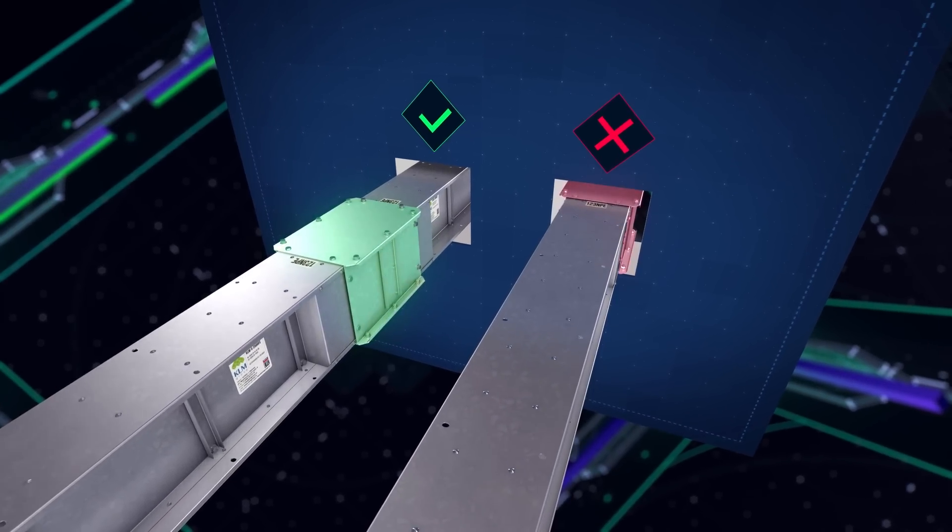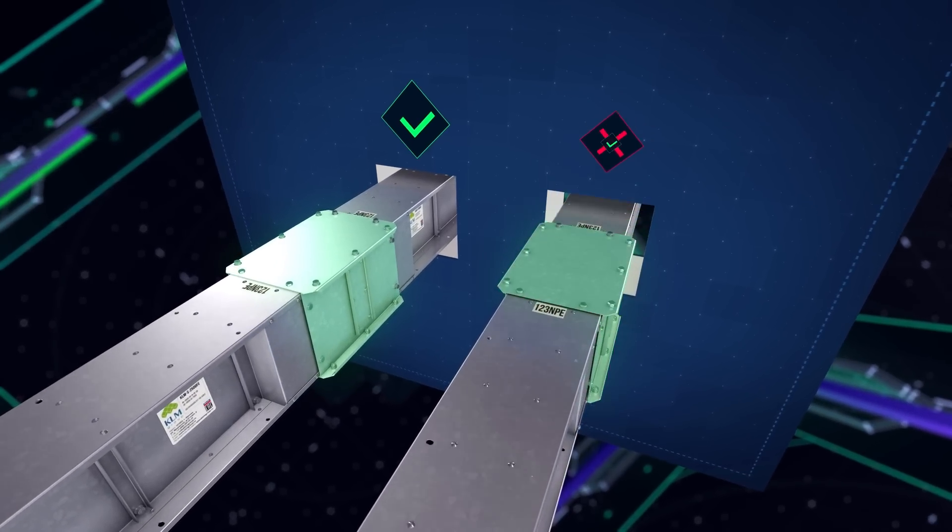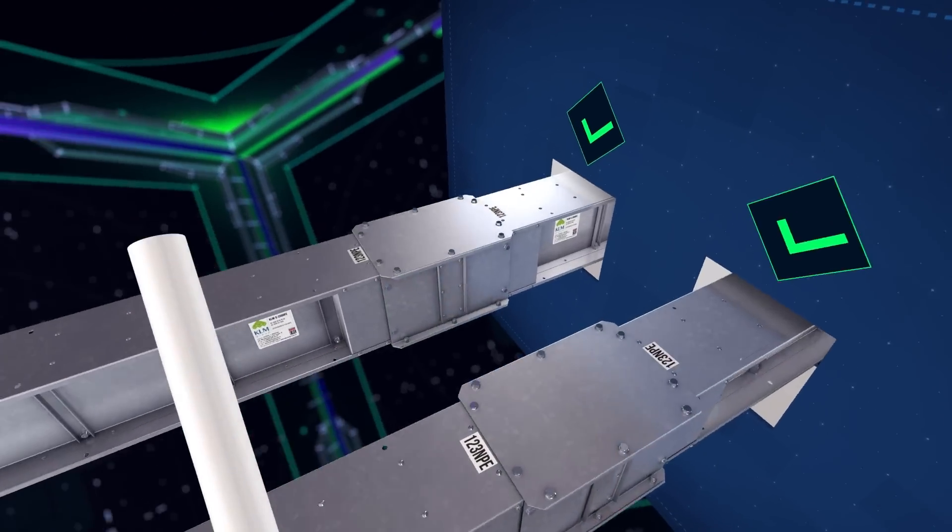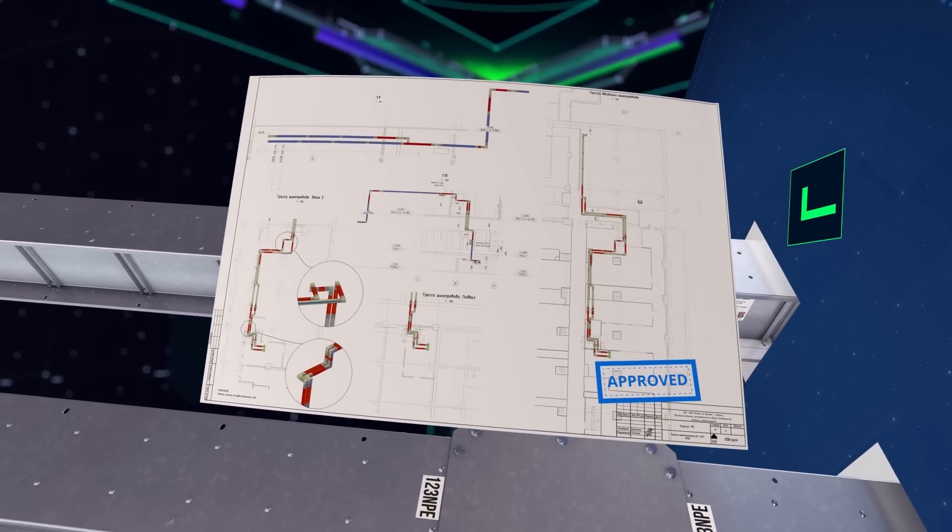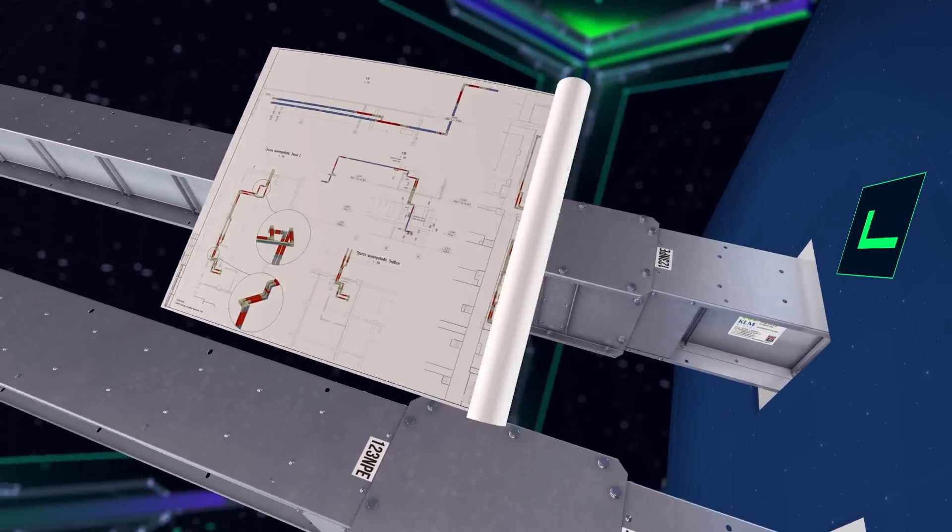Junction units must not be placed in floor ceiling assemblies or in interior partitions of a building. Care must be taken to ensure that the bus bar trunking system is assembled according to the approved drawing unless the contract supervisor indicates otherwise.